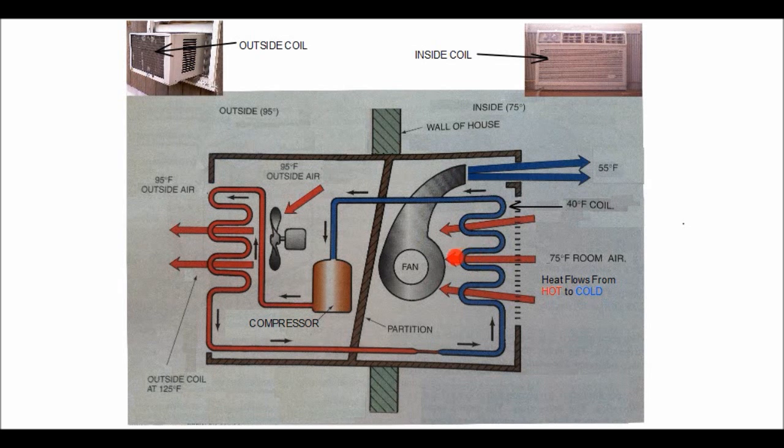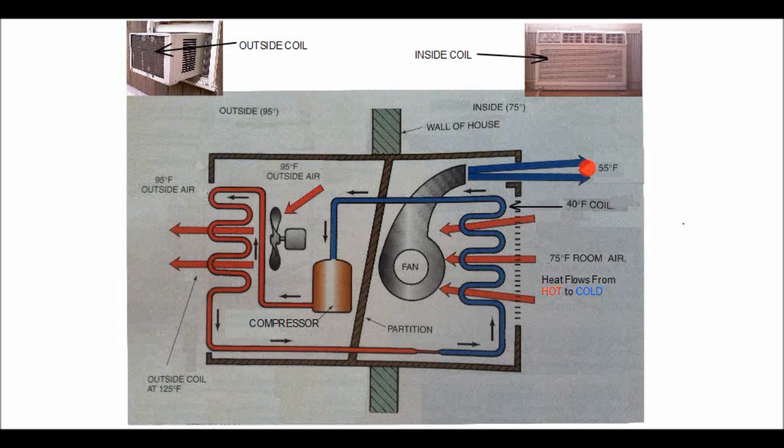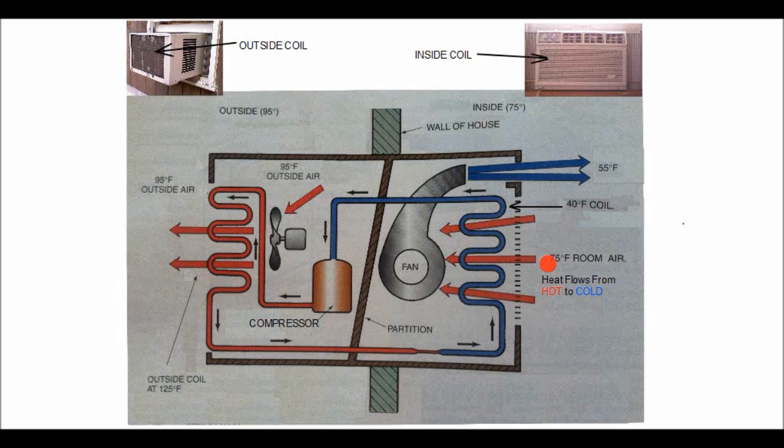And when the air ends up on the other side of the coil, some of the heat has been removed, and that air comes out on the other side of the coil at about 55 degrees. Most of your air conditioners are going to cool the air by about 20 degrees. If you can get 21, 22, it's doing really well. You'll see on the older air conditioners, it's somewhat below that.